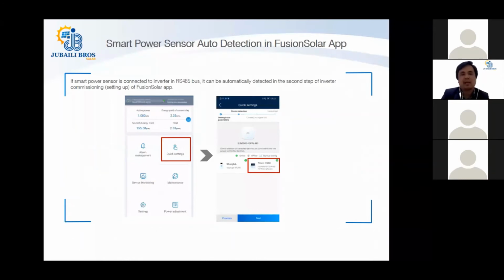Smart power sensor auto detection in Fusion Solar app. When you are commissioning your PV system, the first phase is to detect the devices and commission your PV system. The first thing is to detect, and when you put in one of the devices in your PV system, the serial number of that device, then all the related other inverters and devices that are connected, which are from Huawei, will be automatically detected.